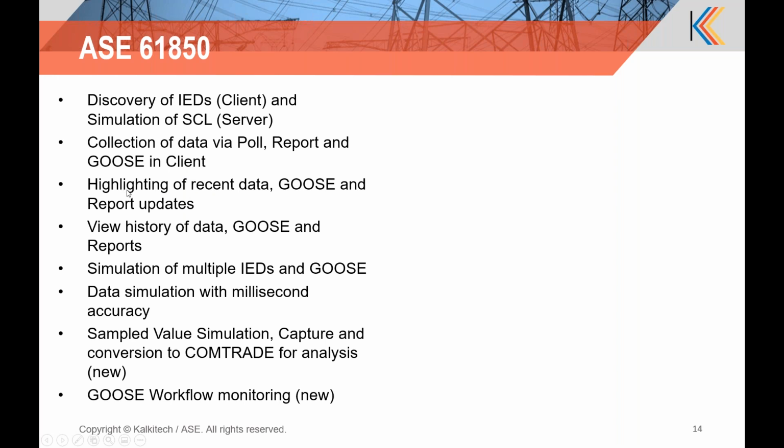The main functionality of the client is the capability to highlight the changes as soon as they are available in the machine. So the user interface will allow the user to see the changed data very easily. We also keep the history of point changes, GOOSE collected into the system, and also the reports. So at any point of time, we can go back and see what happened over a period of time. The main capability of the server simulator is to simulate multiple IEDs. So we can virtually simulate a substation with multiple IEDs on a PC. We also have the capability to publish and subscribe GOOSE messages in the server.